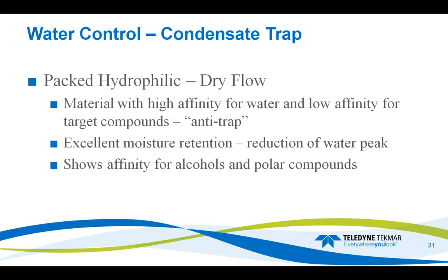Packed hydrophilic columns give excellent moisture retention, so they do contribute greatly to the reduction of our water peak. However, they can show an affinity for alcohols and highly polar compounds. Therefore, they're not good for oxygenates analysis, for instance.